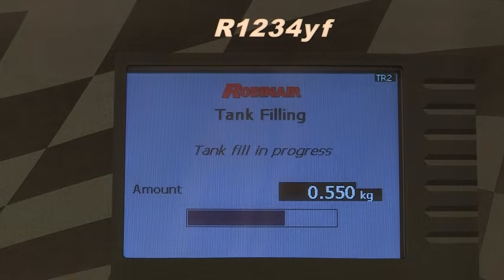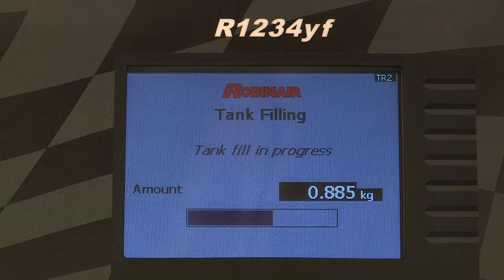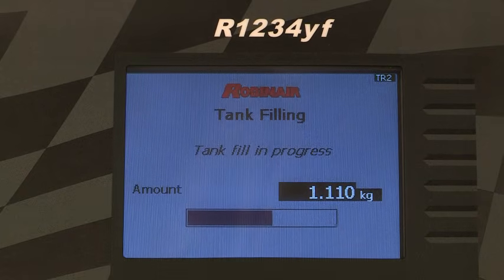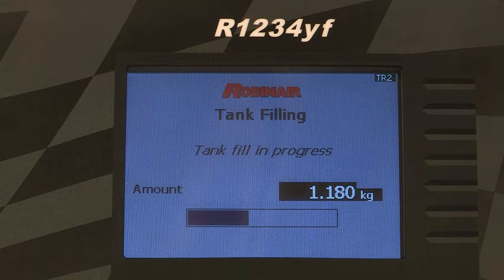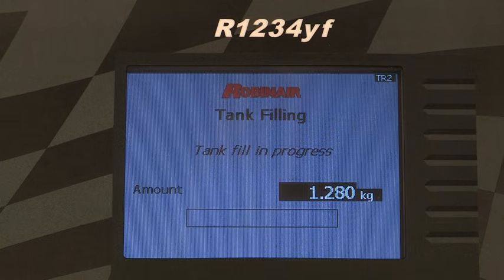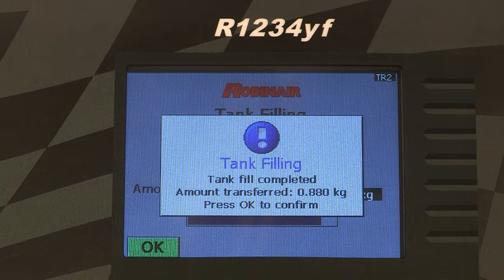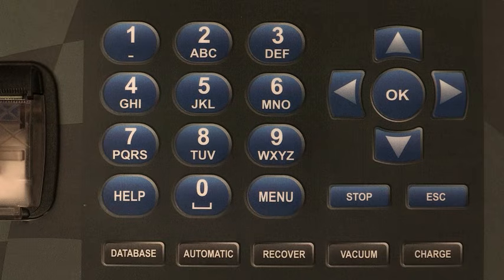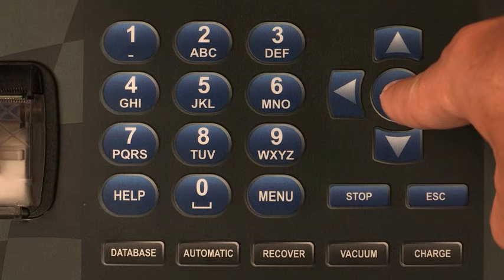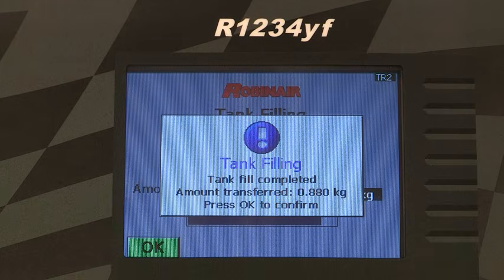Add at least 3.6 kilograms of refrigerant to ensure enough is available for charging. This process takes about 15 to 20 minutes. The machine stops when the designated amount of refrigerant has been transferred to the ISV or when the source tank is empty. Press OK to return to the Functions menu. The machine is now ready for operation.